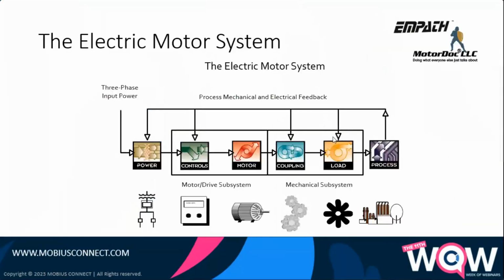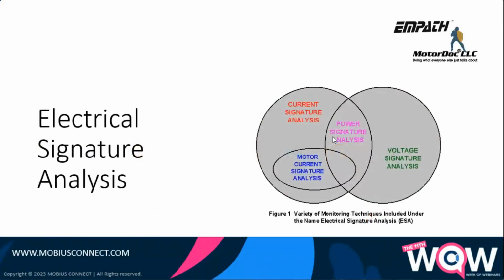So let's take a look at electric motor systems in particular. So we have in an electric motor system, incoming power, controls, motor, coupling, load, and process. We won't do anything further upstream, but we will count downstream. This is what you would see with electrical signature analysis all at once. That's one of the reasons I like it. And electric signature analysis looks at current, looks at voltage, looks at power quality. By definition, in order to do electrical signature analysis, you're using a power analyzer in any case.